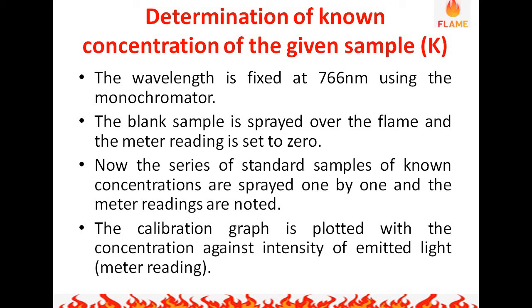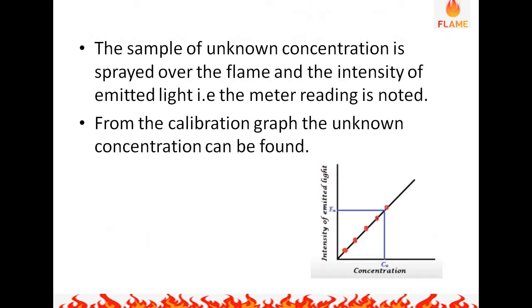For the blank, distilled water is used and the meter reading is set to zero. Next, a series of standard solutions of known concentration are prepared. These solutions are sprayed one by one in the flame photometer and the readings are noted. Using these readings, a calibration graph is plotted with concentration on the x-axis against the intensity of the emitted light, or meter reading, on the y-axis. Then the sample of unknown concentration is sprayed over the flame and the meter reading is noted.